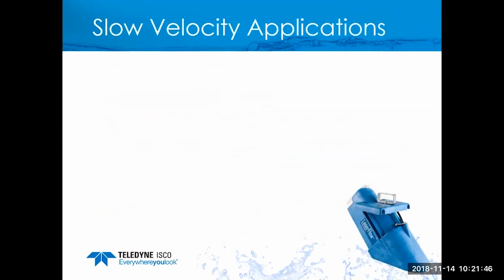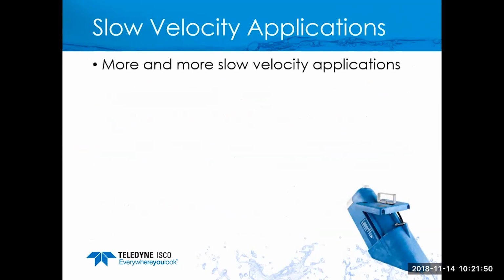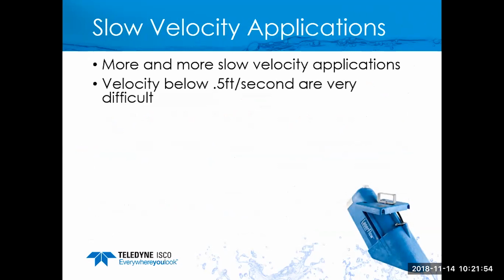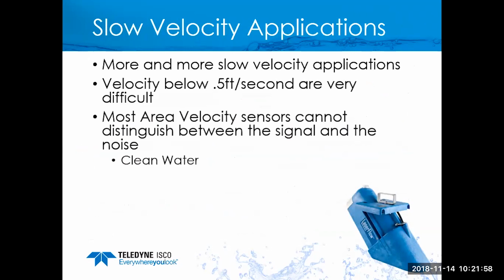Okay, so let's talk now about the opposite end, the slow velocity applications. Seeing more and more of these type applications. Anything below a half foot per second can be very difficult to measure. Most AV sensors are going to struggle with that because it's so slow, you have noise at the low end and you won't be able to distinguish between that signal to noise ratio. So that can happen with slow water, and it can also happen with very clean water.